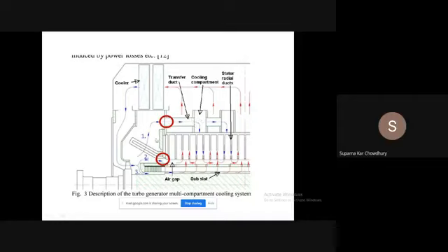The main thing is that we are entering the coolant into this air gap. Now the total system is enclosed, but the shaft should come out. When the shaft comes out, it is difficult to seal here. So normally it has to be sealed properly with liquid oil sealed glands, so that there is no leakage of coolant from this point.